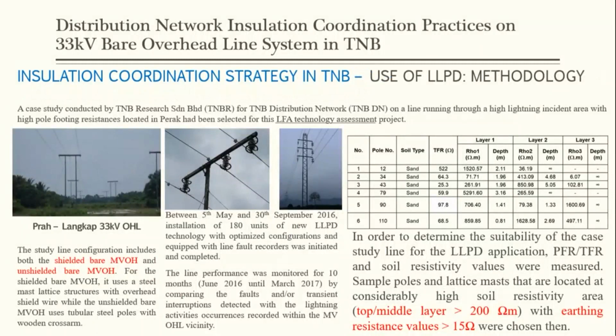Okay, a case study conducted by TNB Research for the TNB distribution network on a line running through a high lightning incident area with high pole footing resistance located in Perak was selected for this LLPD technology assessment project. The line in question is the Prah Langkat 33 kV overhead line. The study line configuration includes both the shielded bare medium voltage overhead line and the unshielded bare medium voltage overhead line.